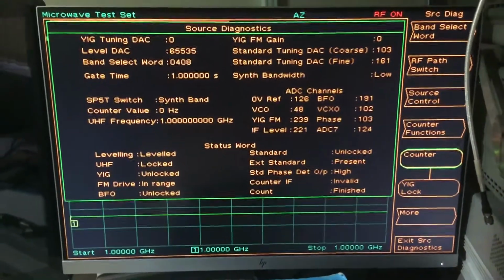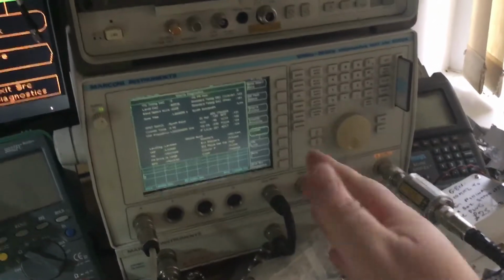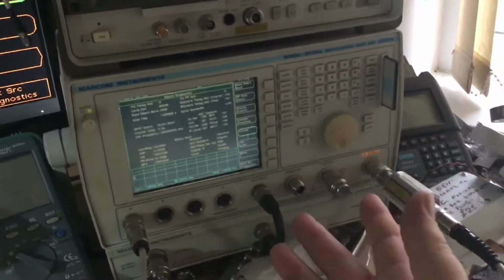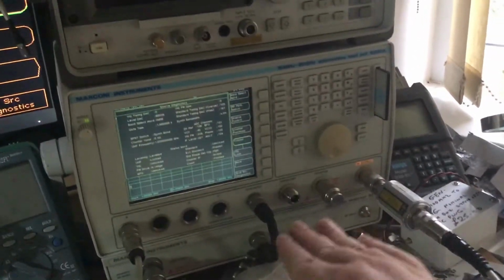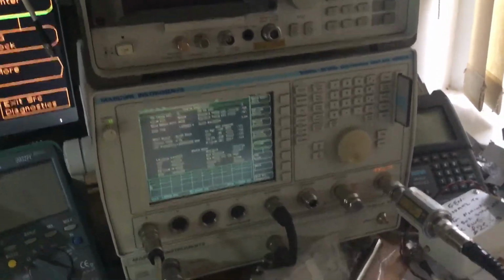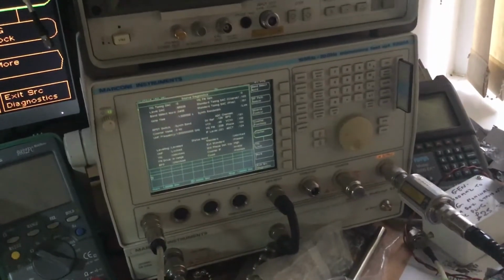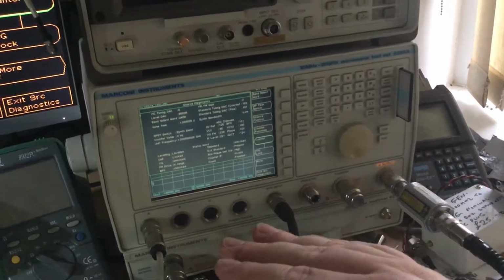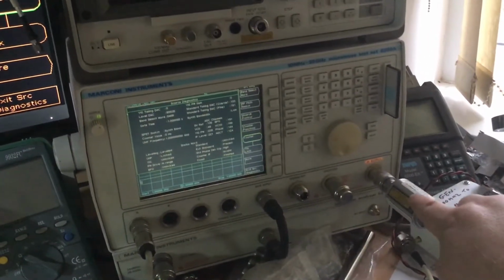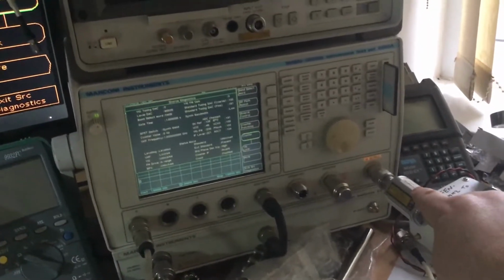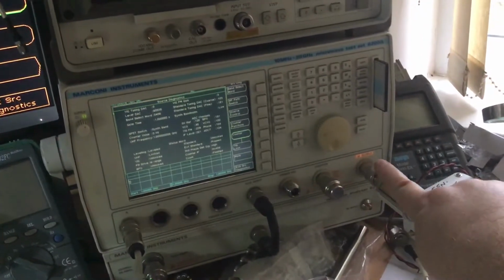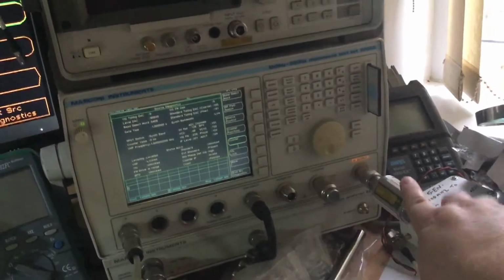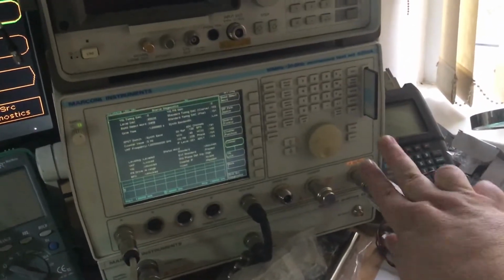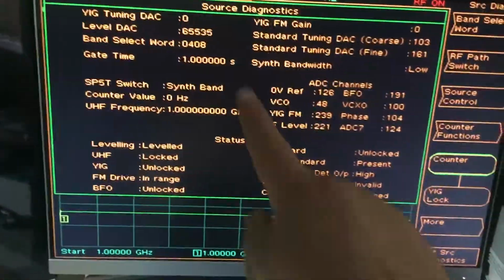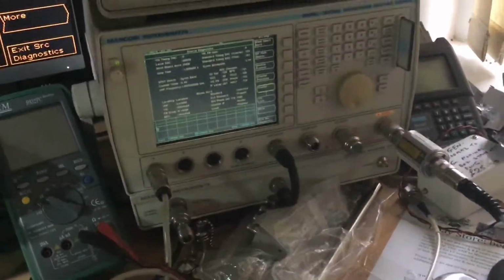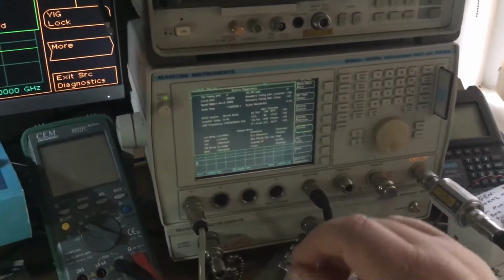For example, say you wanted to calibrate it narrowband from 1 gigahertz to 2 gigahertz, just for argument's sake. It'll output a 1 gigahertz signal at different RF levels, and it knows that if it's going to calibrate a 0 dBm level at 1 gigahertz, it'll adjust the voltage to the diode attenuator that we were showing in the previous videos. It increases or decreases the RF output proportionately until it gets to 0 dBm read by this sensor. Once it gets to 0 dBm, whatever value this DAC might be, it saves that to memory within the test set, and then it moves on to the next level in 1 dB steps.